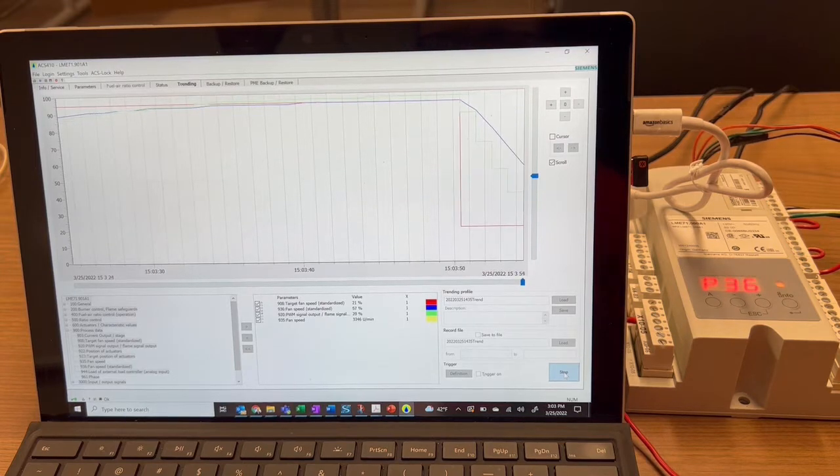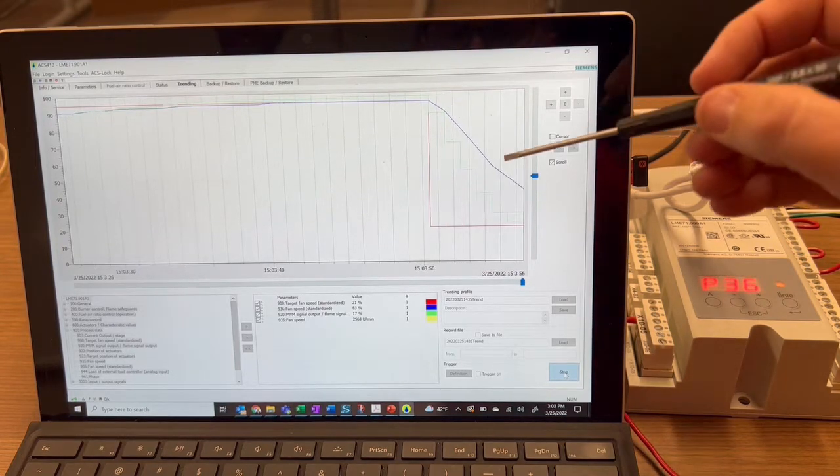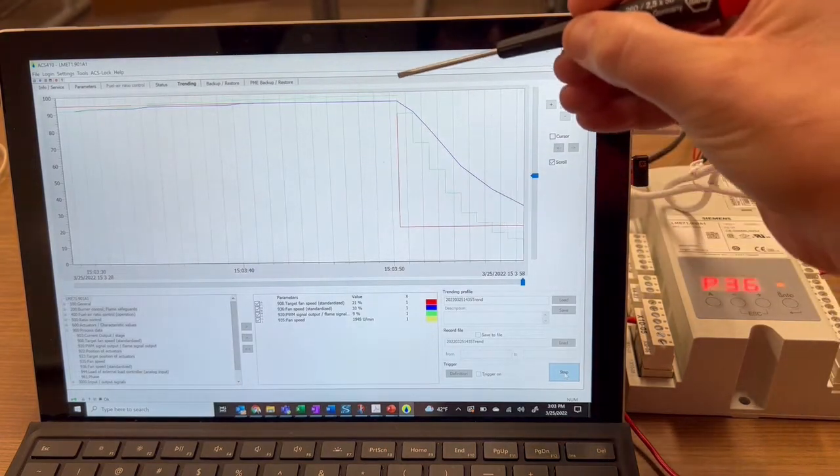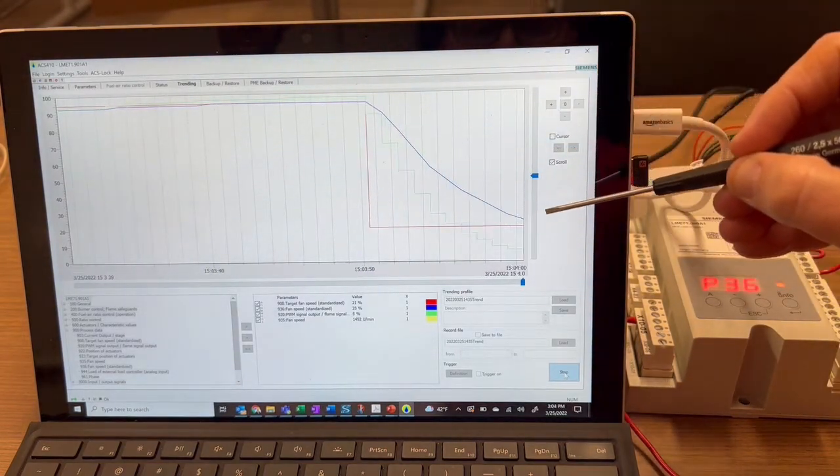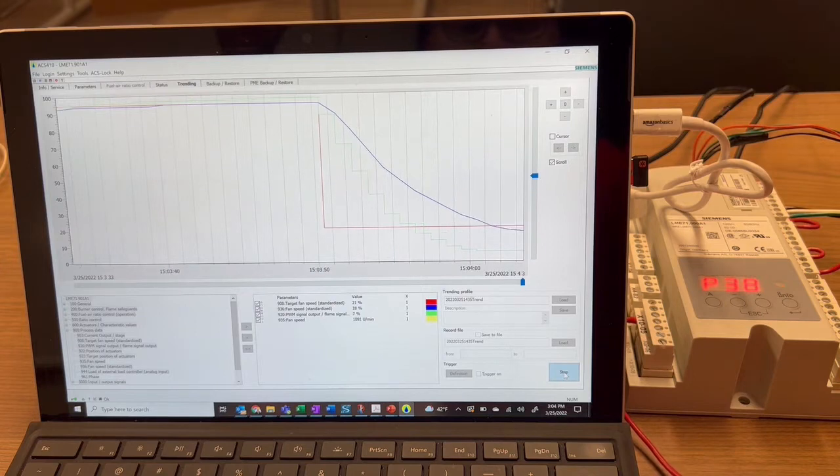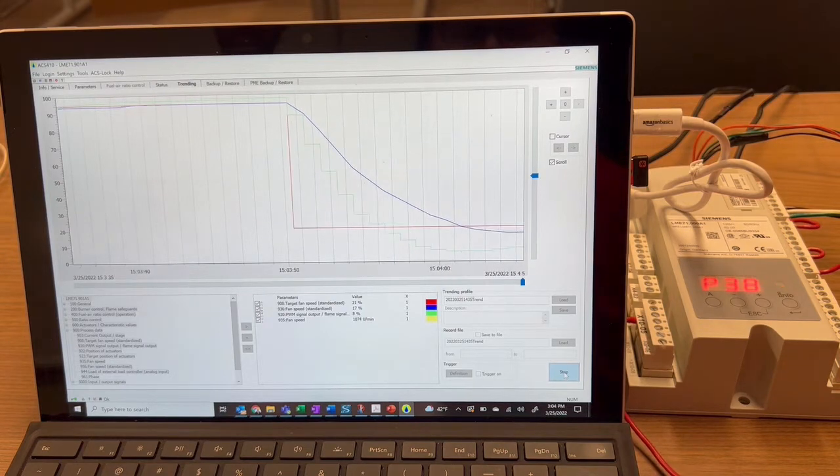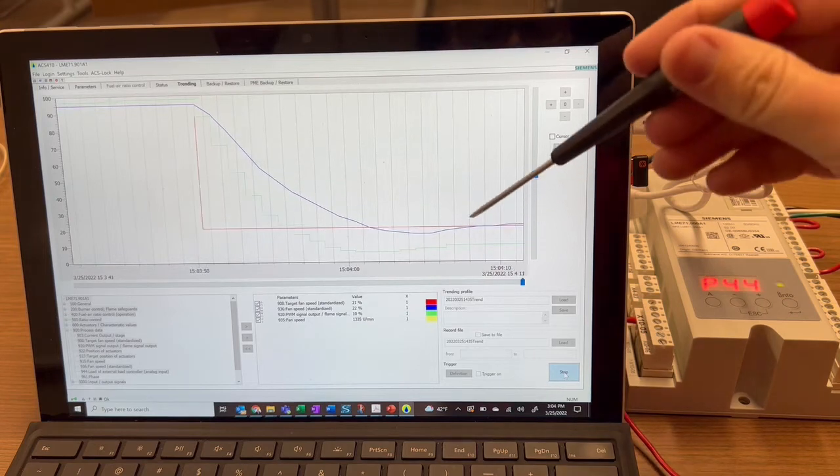We're now driving to ignition speed. We see the target speed dropped and the actual speed, the blue, is going down. Now the trial for ignition. The blower speed undershoots and then it settles out a little bit.